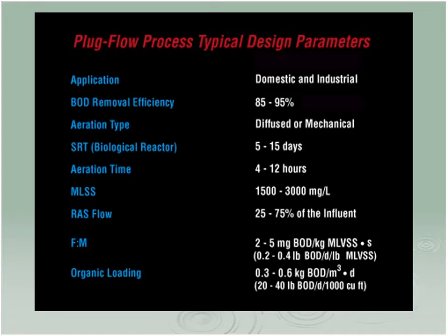So our application, domestic industrial, has two of all of these. 85-95% BOD removal is simple. Be done in no time at all, really. Aeration type, doesn't matter, diffuse or mechanical. Our SRT, 5 to 15 days. Now, if I'm only concerned with getting my BOD down below 30 or 15 or whatever the number is, 3 to 5 days is more than adequate. You do the job very, very quickly.